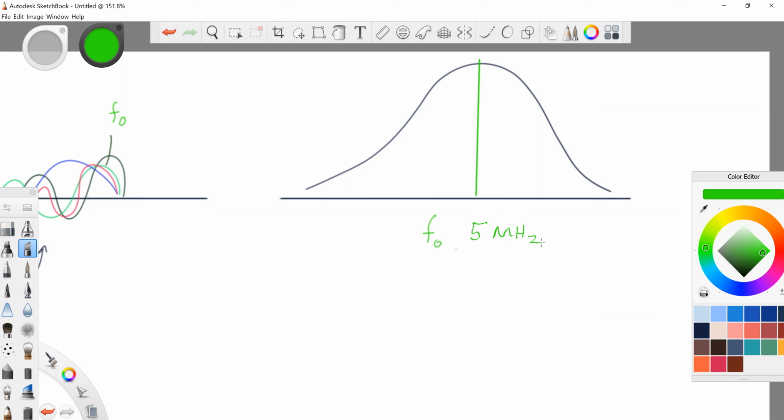Okay, so 5 megahertz is the center frequency, the happy place frequency. This question says that it's as high as 6.5. Let's see, what was my highest frequency? I think it was red. That'd be the 6.5, and let's just say that's right about here. 6.5 megahertz. And my lowest was definitely that purpley bluey.